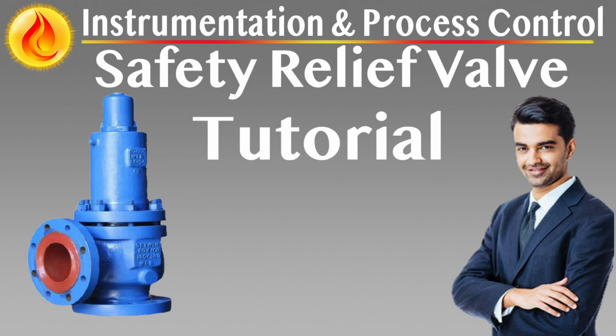2. Supplemental load mode: spring set at 100% of design pressure. Instrumentation initiates opening. Failsafe open at 110% of set pressure. 3. Combined mode: actuator augments a 100% spring setting. Allows margin reduction while maintaining redundancy. Use of these valves may require special approval and instrumentation reliability studies.